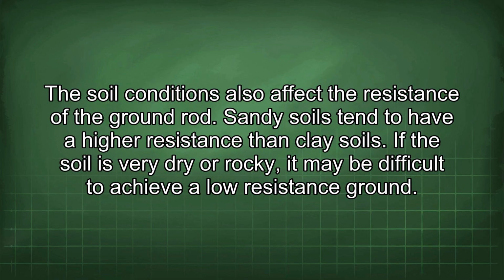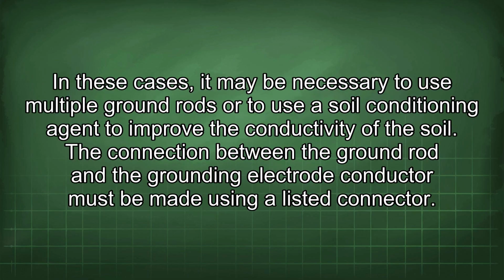The soil conditions also affect the resistance of the ground rod. Sandy soils tend to have a higher resistance than clay soils. If the soil is very dry or rocky, it may be difficult to achieve a low resistance ground. In these cases, it may be necessary to use multiple ground rods or to use a soil conditioning agent to improve the conductivity of the soil.